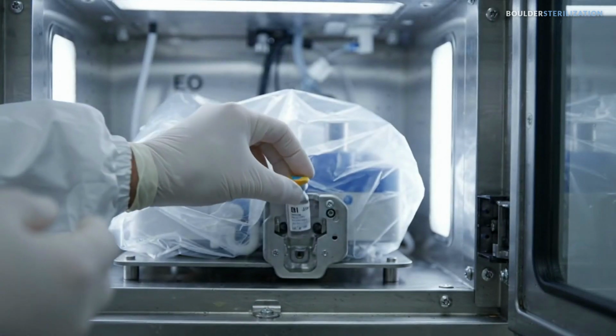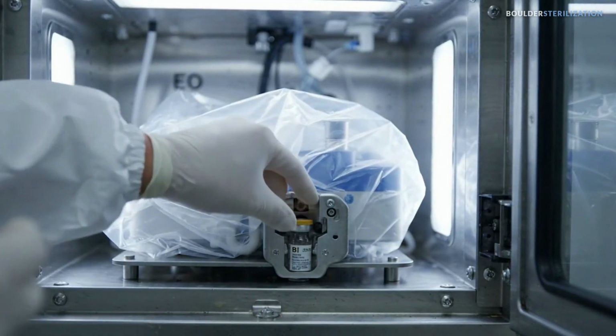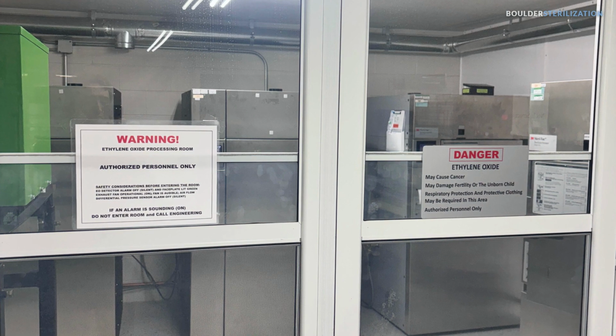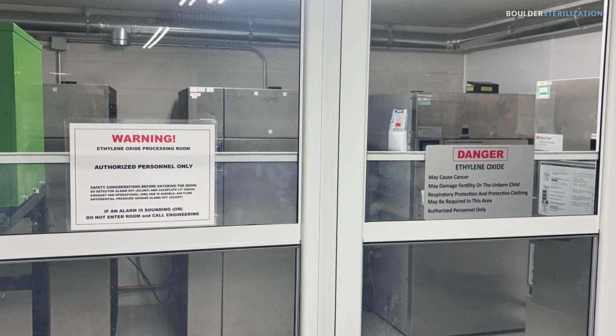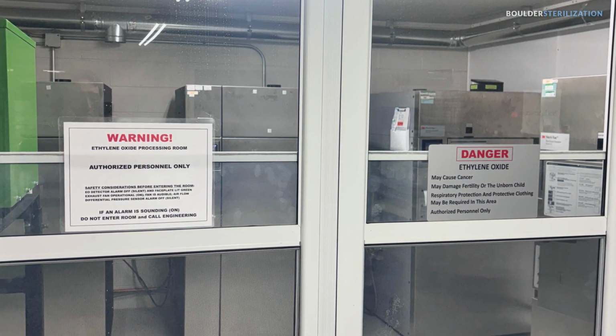The trick is right there in the name. We run the cycle at half the gas exposure time of your real production cycle, and we put those indicators where the gas has the hardest time reaching. Not just the hardest spot to get your hand into, the hardest spot for the gas, deep inside the device, in its most shielded cavity. And then we set those devices in the hardest to sterilize locations in the chamber itself. Worst case, inside, worst case.